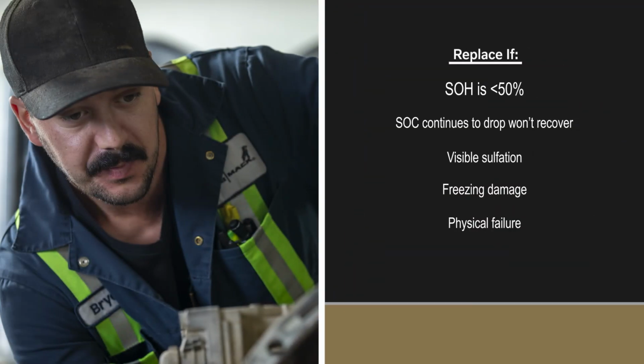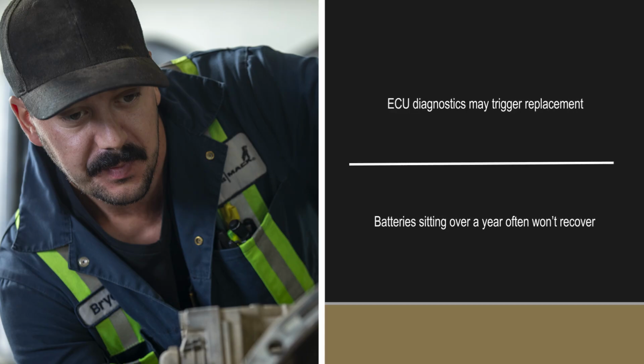So when do you repair? When do you replace? If the state of health is at 50% or lower, if the state of charge continues to drop and won't recover, or if there's visible sulfation, freezing damage, or physical failure, it's time to replace. ECU diagnostics may also trigger replacement, and batteries left sitting for over a year often won't recover.